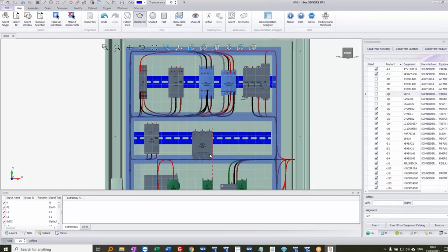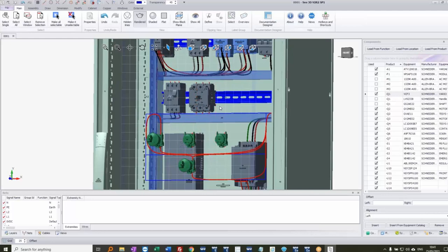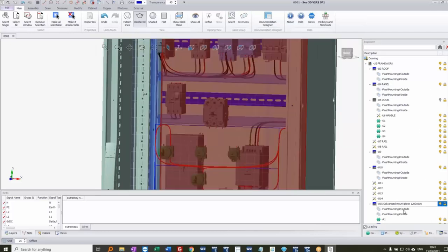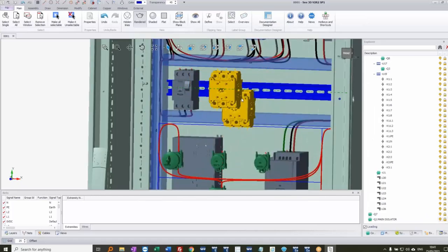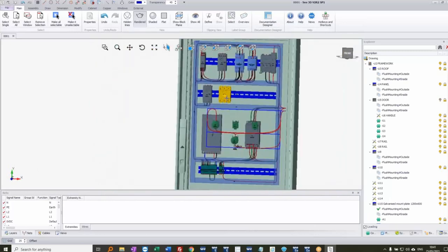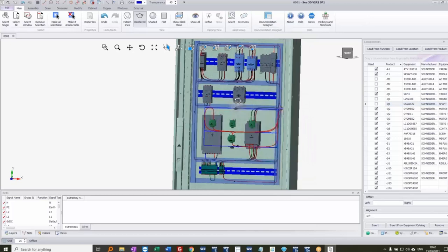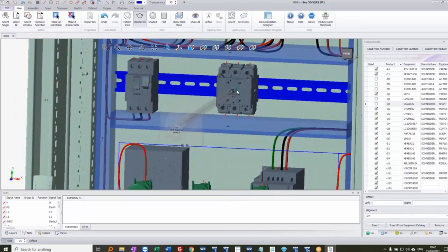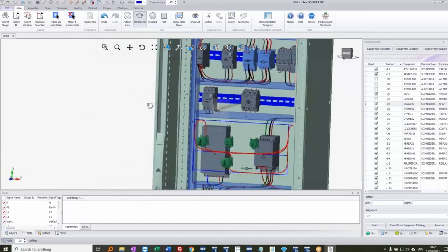I'll place the disconnect switch manually. I notice my active plane is currently the door, so placing it puts it on the door — not where I want it. Going back into the Explorer, I click the gear plate and set its outer surface as the working plane. I double-click the switch and snap it into position on the gear plate. Then I place the shaft — as I move over the existing device I can see a mating plane square, and clicking places it exactly in the right position.